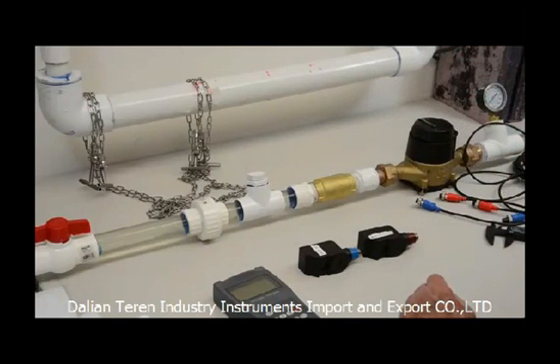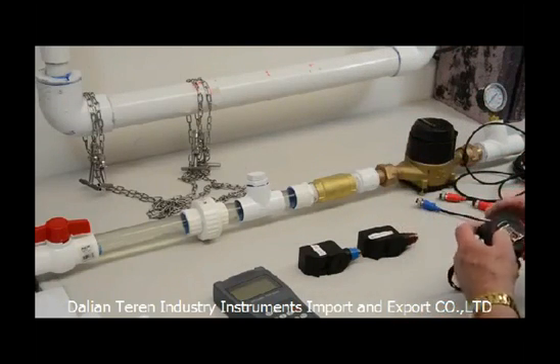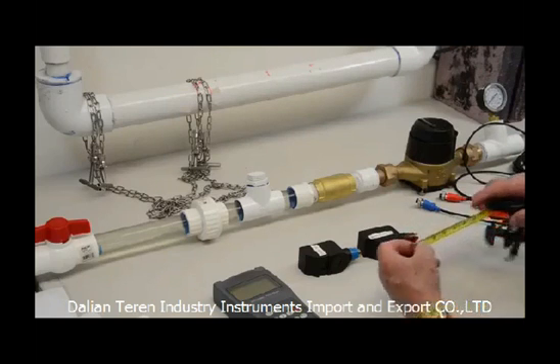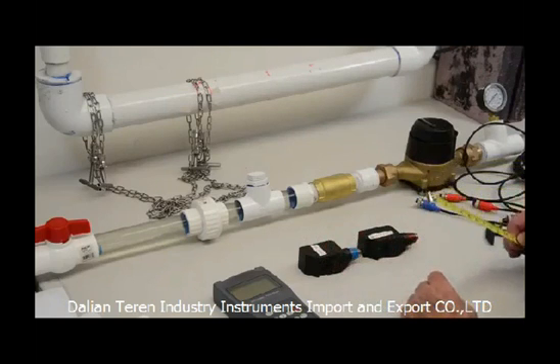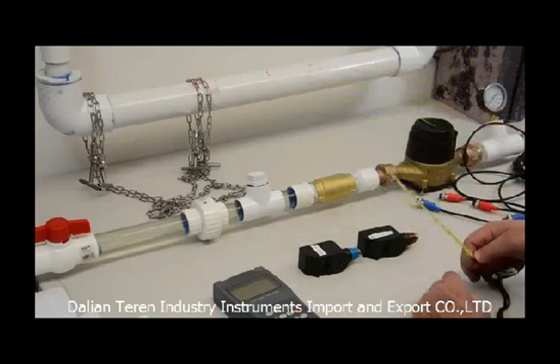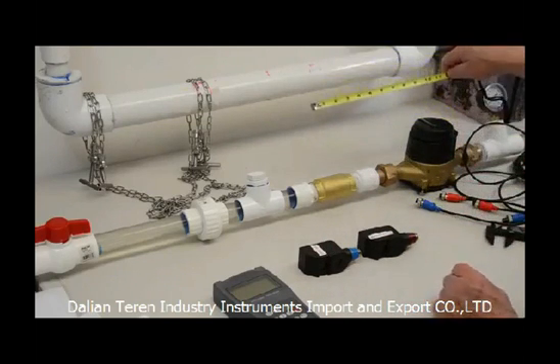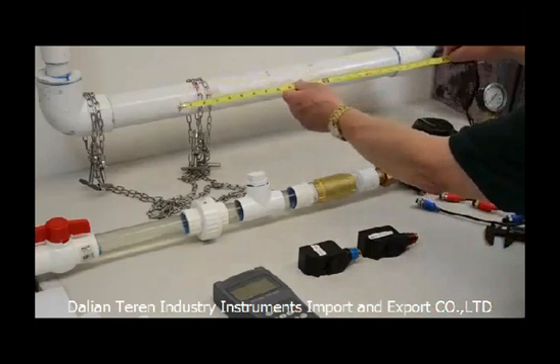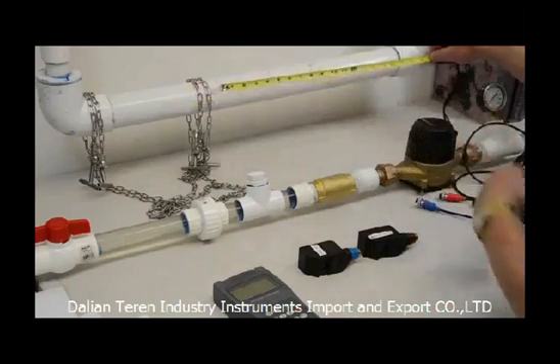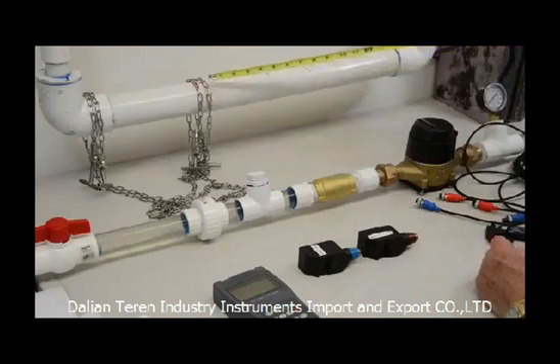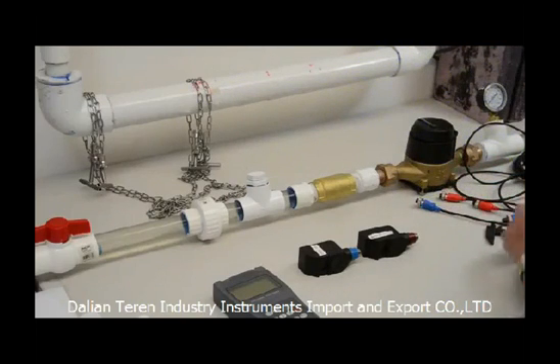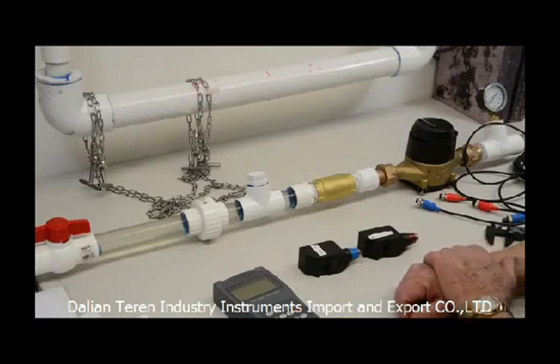Another thing that's quite important is that the instructions in the manual say that you need to be 10 diameters from any elbows or anything. In this case, I'm 2 inches, and so I want to be about 20 inches from the elbow, and so I'm in this area right there. That'll give me the most accuracy. I'm going to hook up these two transducers.